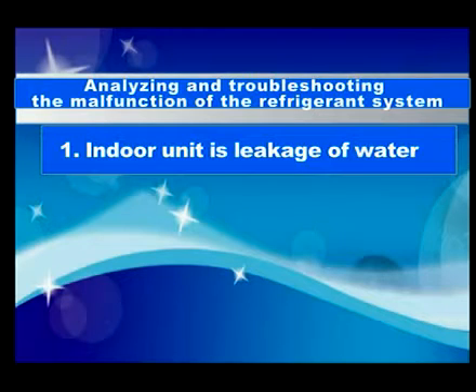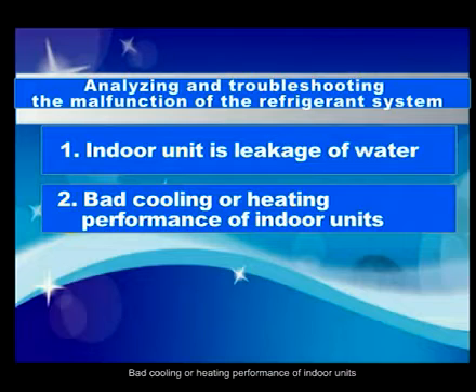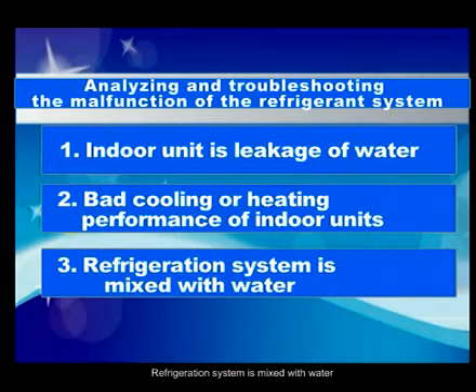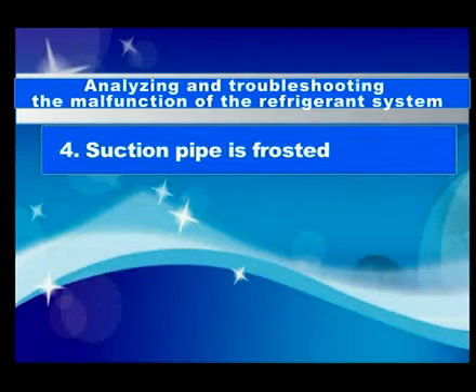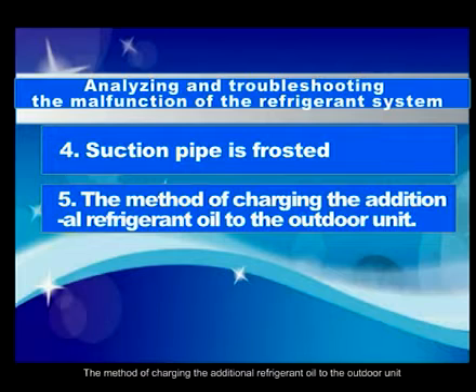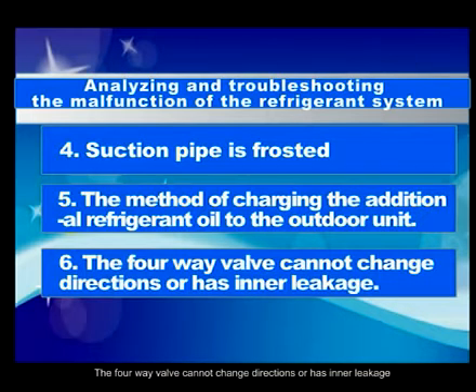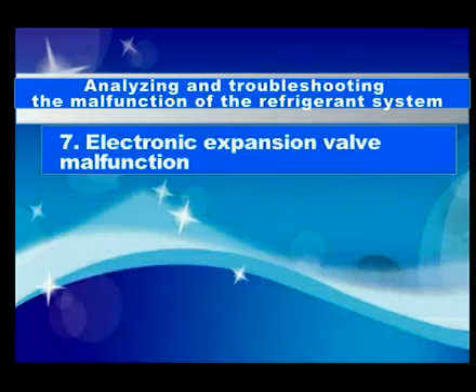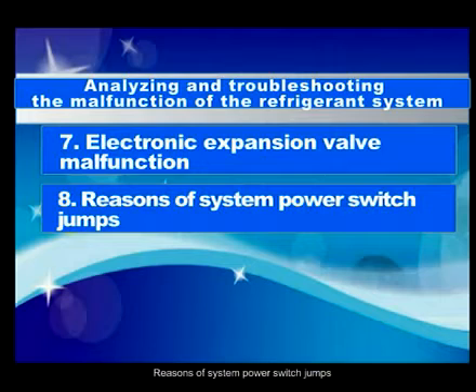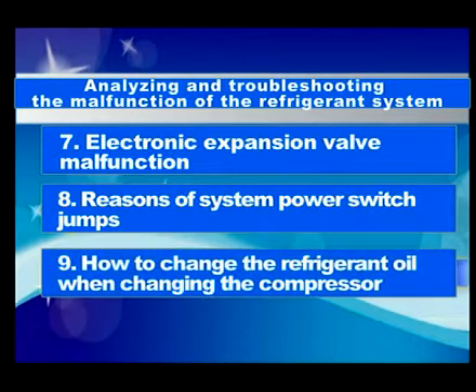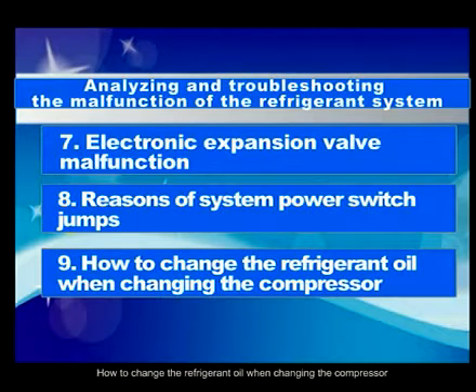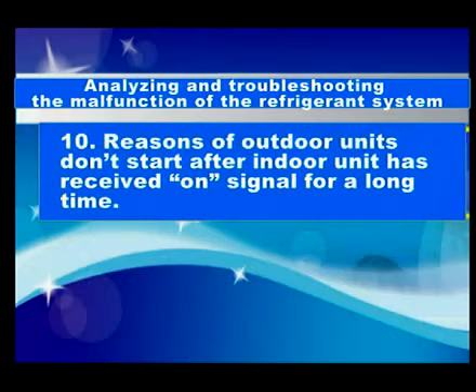Indoor unit is leakage of water. Bad cooling or heating performance of indoor units. Refrigeration system is mixed with water. Suction pipe is frosted. The method of adding additional refrigerant oil to the outdoor unit. The four-way valve cannot change directions or has inner leakage. Electronic expansion valve malfunction. Reasons of system power switch jumps. How to change the refrigerant oil when changing the compressor. Reasons of outdoor units not starting after the indoor unit has received the on signal for a long time.